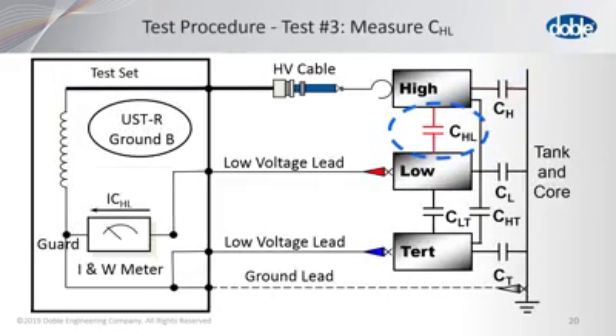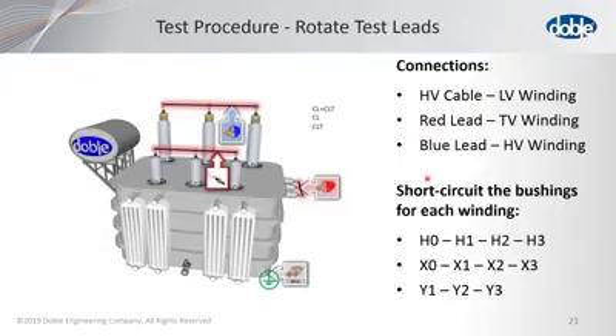Then we go to test number 2, where we measure only CH. Then we go to test number 3. We get test CHL. Now notice this is all automatically done by the test set. You just have to make the right connections. Then we rotate the leads, and this is quite easy in that whatever lead is on the high side, you will move to the low. Whatever's here, you move to the tertiary, and whatever's in the tertiary, you move to the high. So now the high voltage lead will be on the low voltage winding, the red will have the tertiary, and the blue will be on the high side.